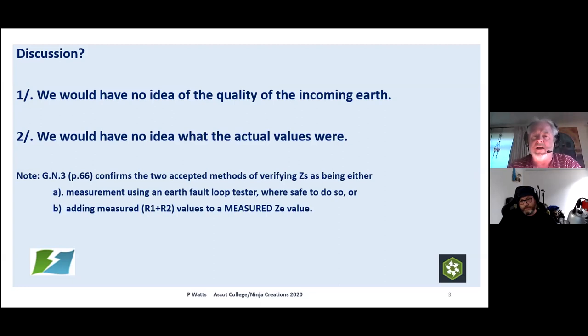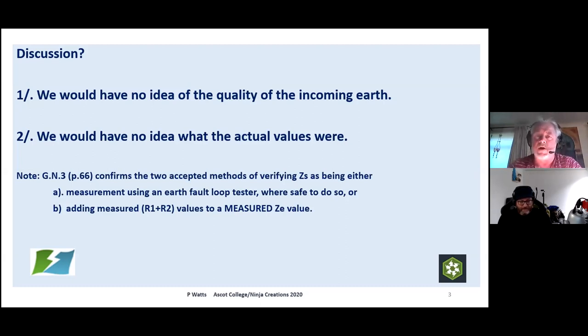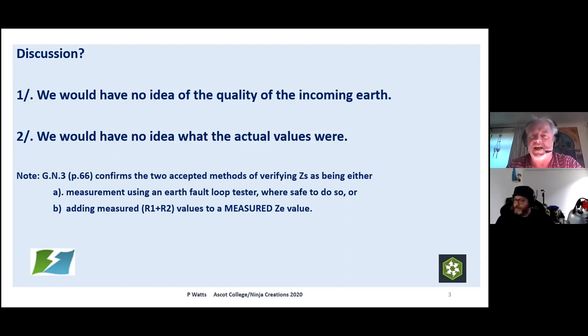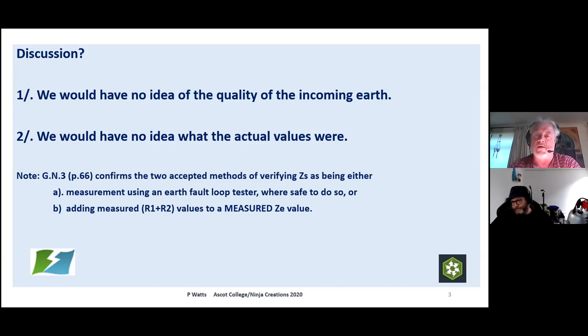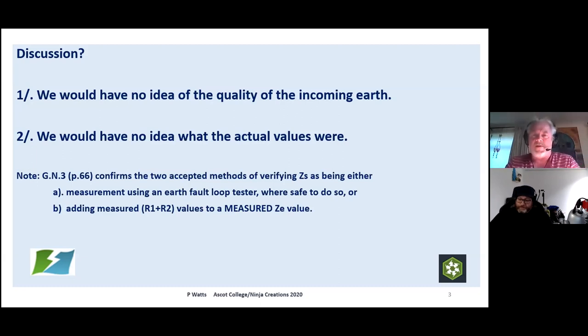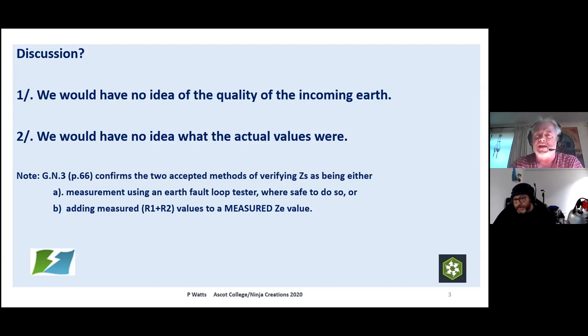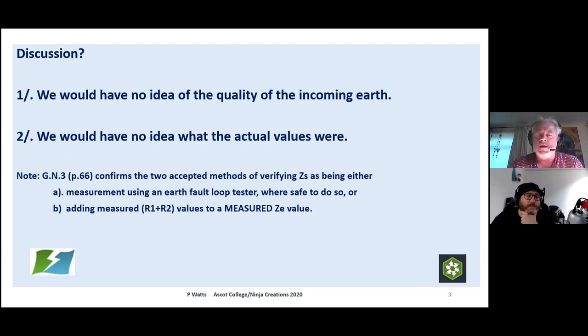If you're doing earth loop impedance tests on socket outlets, surely it's a safe test to do. The other way is to add your measured R1+R2 — measured during the dead test — to a measured Ze value. That's a measured value, not a value by inquiry, not a value by sticking your finger in the air. We're going to do a proper live test on the incoming supply and get a proper Ze value. That is what it says in guidance note 3.